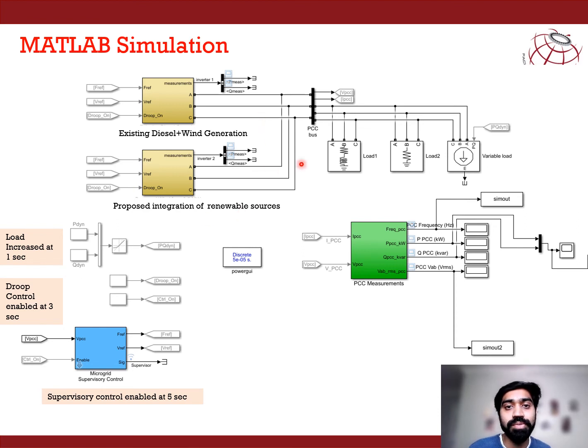And these two sources are connected with the point of common coupling bus, and then it is connected with the load. So we have taken commercial load, residential load, and there is a variable load too with this PCC. So we'll simulate the effect of this variable load along with the droop control method. Here at 1 second we will increase the variable load, and at 3 seconds droop control will be enabled to check the frequency deviation, and at 5 seconds of simulation time supervisory control will be enabled, of course, to check the frequency deviation.